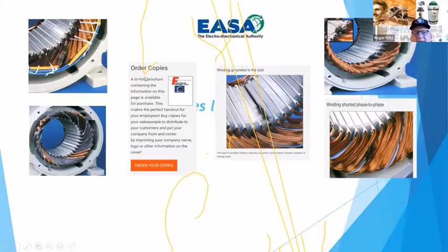It also can happen because the insulation itself, the motor may have been running hotter, and so what happens is that it starts breaking down that paper. It's a paper. A lot of times, like in Class H insulation, which is very high temperature, that's called Nomex. They also, original motors were designed with different characteristics, like an A, most are a B, C, and D design. But the insulations were B, F, and H, meaning that the B was rated to really not run much over 120, 130 degrees, or it had failures.